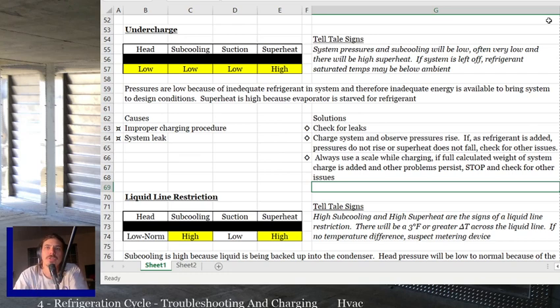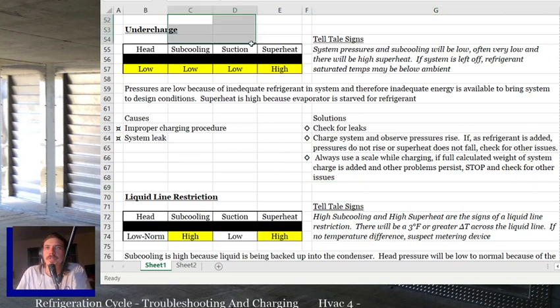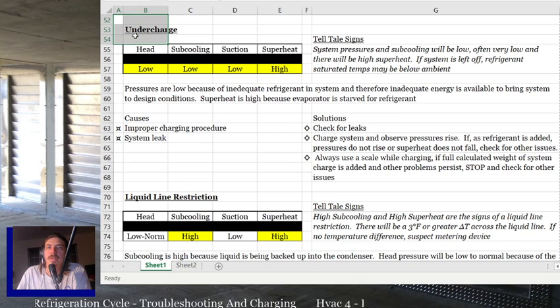Or if you start charging it and your head pressure starts shooting up real fast, it was low and now it's just climbing like a rocket, then you probably weren't actually undercharged. You need to figure out what else was going on, because you probably just had a misdiagnosis. But undercharge is pretty easy other than that. Just don't let other things that cause high superheat or low suction pressure trick you into an undercharge.